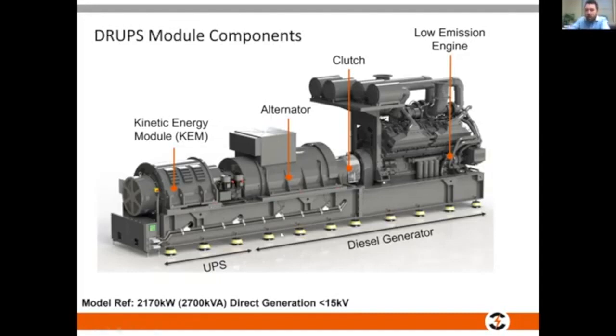And it doesn't matter what technology you use. I've made reference to static UPS. If you do need that long-term power, you need a diesel generator. Now, what I've done, of course, or what we've done, is mechanically coupled my flywheel. This flywheel, in this setup right now, is maximum about 2.2 megawatts, which is about 2.7 MVA, and it can go up to 15 kV.